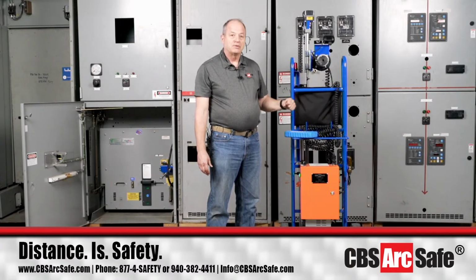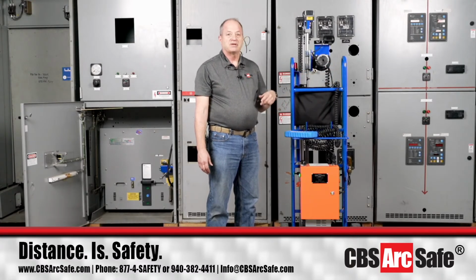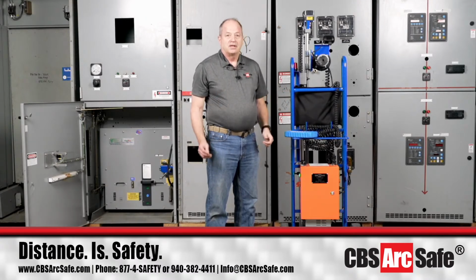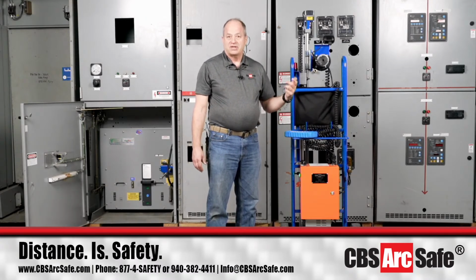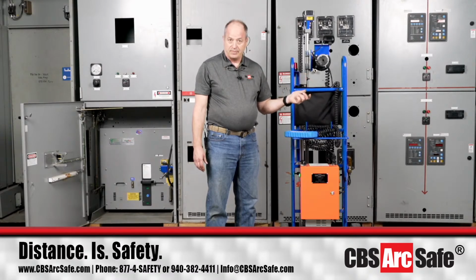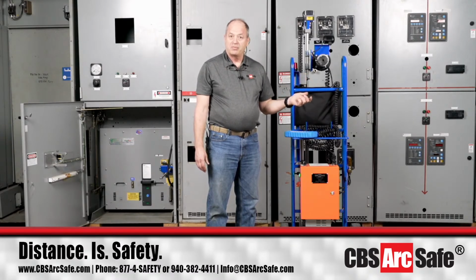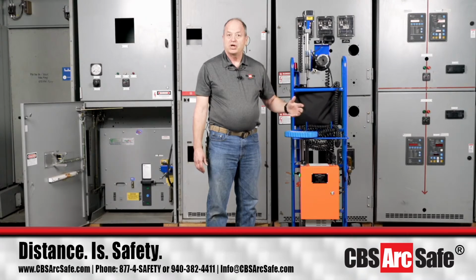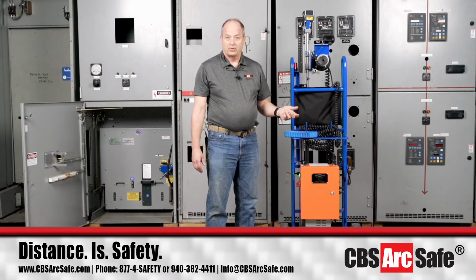ITE HV gear: 15.4, 15.7, 15.4, 15.7, 15.7, 15.7, 15.7, and the last one was 25.8. At that time, that's how we helped the power plant determine they had a problem with their switchgear, because we could show that it physically took more force.